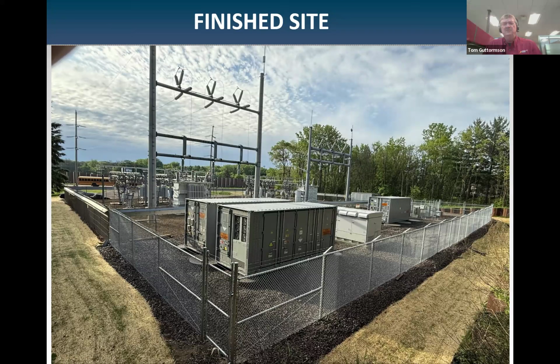The interesting thing was, if you took the cost of the capacity that would have been added by putting in new transformers, the dollar per kilowatt of capacity would have been less for the substation rebuild. But that was building capacity that was a gross overkill, capacity we'd likely never use. So this is a just-right-sized system. It got us the capacity we need to defer that transformer upgrade for either many years, or maybe even indefinitely. We don't know, we'll see how that goes. And at a higher dollar per kilowatt of capacity cost, but looking at solving the engineering problem was a cheaper price overall. So that worked out really well.